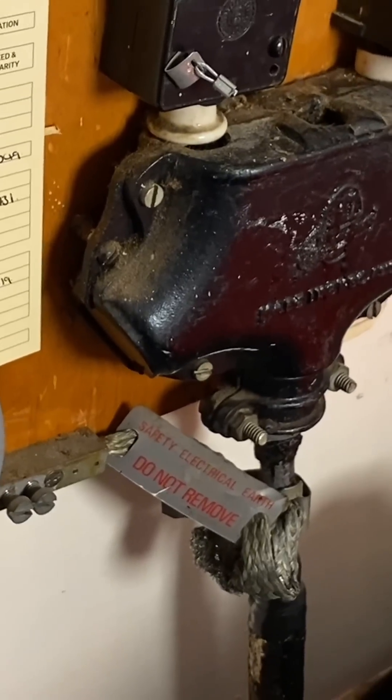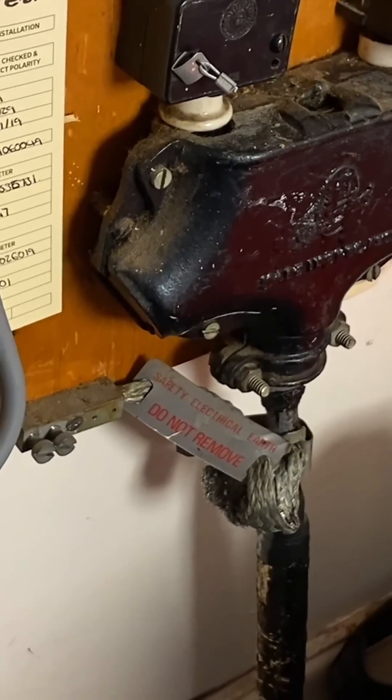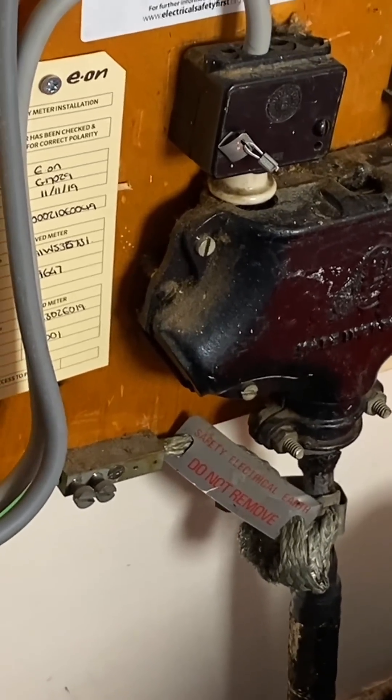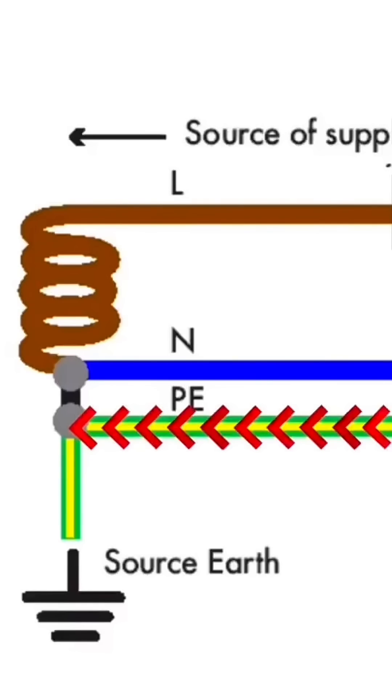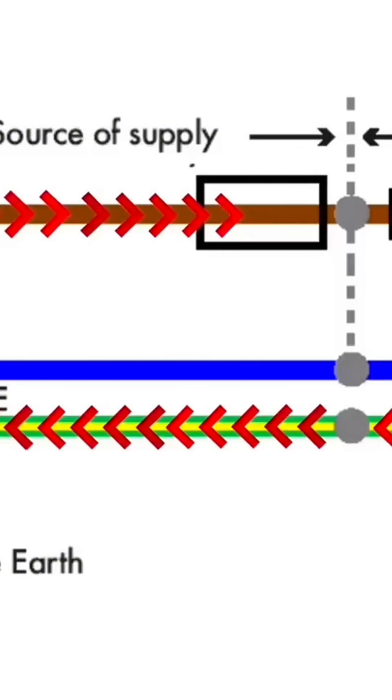The earthing conductor is connected to the lead or steel sheath of the supply authority's cable which becomes live. This is connected to the earth neutral point within the transformer which becomes live. Back round the line conductor completing the circuit.